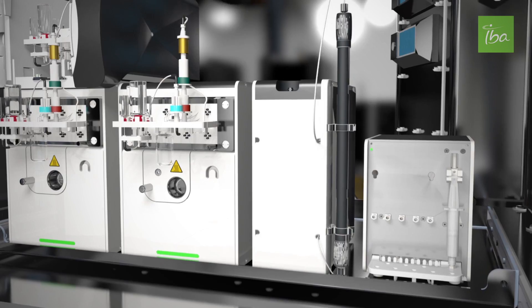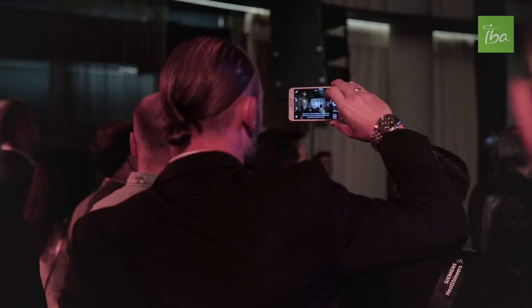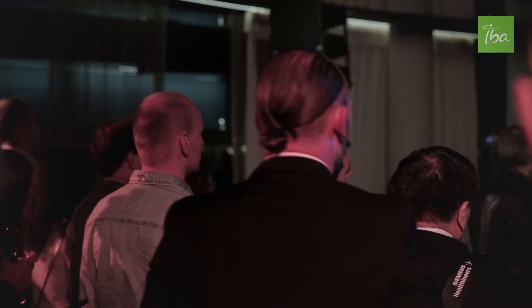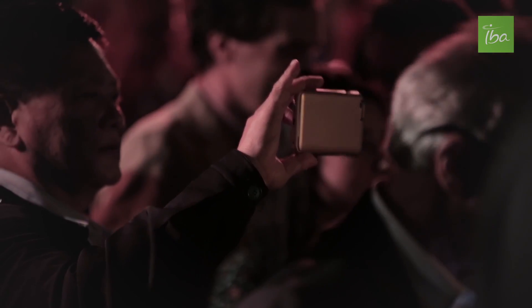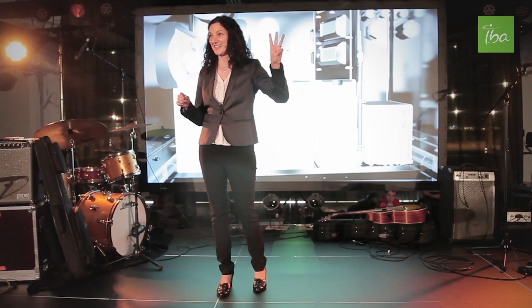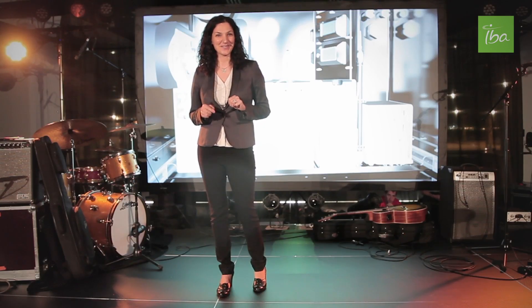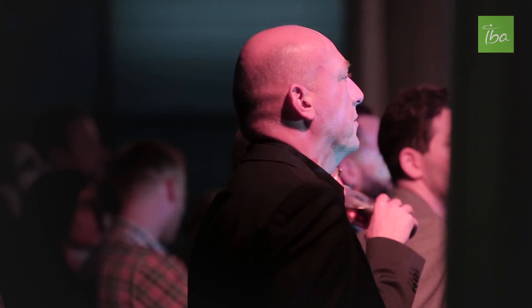The most unique feature of Synthera Plus is the IFP Loader. With it, you can do four consecutive runs on one module without opening the hot cell. And all of this with zero radiation exposure and zero downtime between the runs. Don't forget, Synthera is still the smallest module on the market. You can put up to three modules in a hot cell. So let's do the math: three modules per hot cell times four runs per module equals 12 runs per hot cell without opening the hot cell.